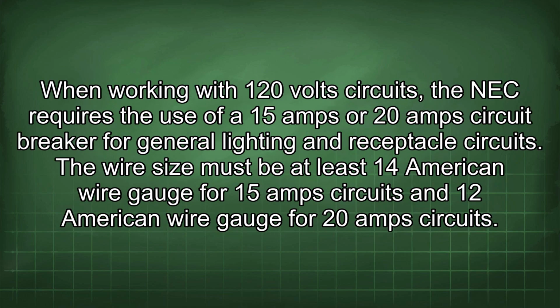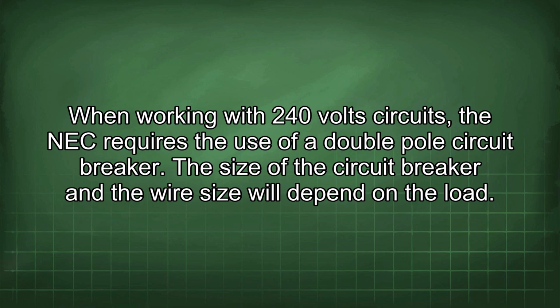When working with 120 volt circuits, the NEC requires the use of a 15 amp or 20 amp circuit breaker for general lighting and receptacle circuits. The wire size must be at least 14 American wire gauge for 15 amp circuits and 12 American wire gauge for 20 amp circuits. When working with 240 volt circuits, the NEC requires the use of a double pole circuit breaker. The size of the circuit breaker and the wire size will depend on the load.